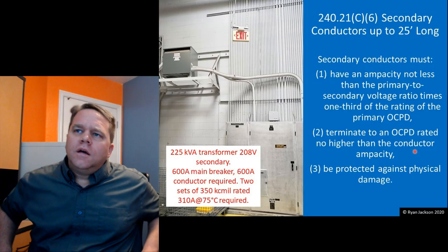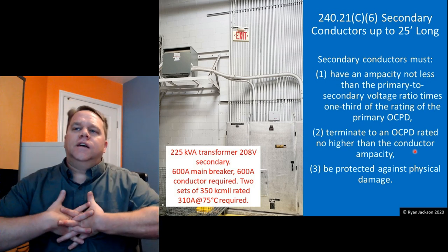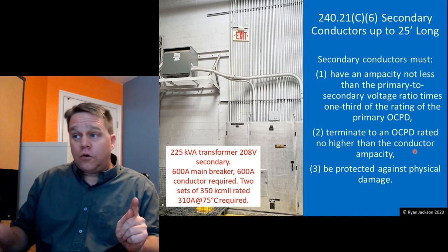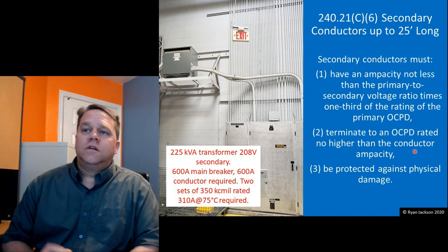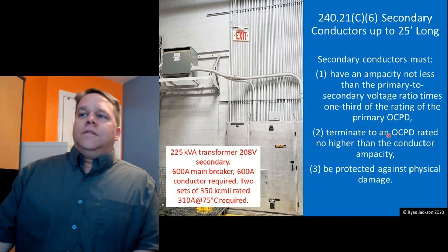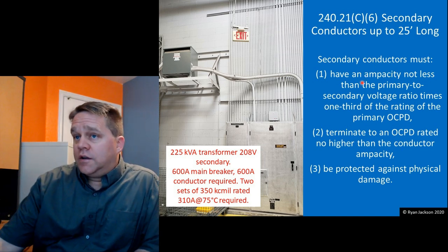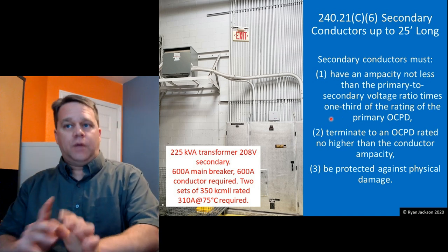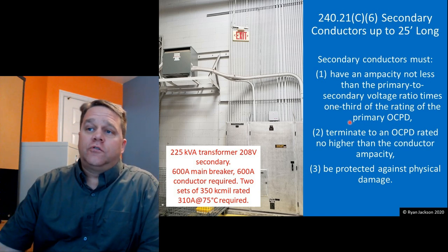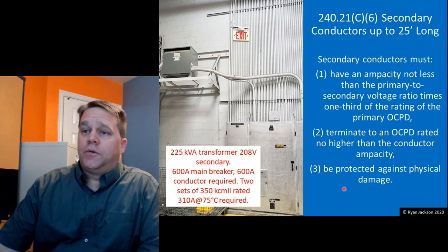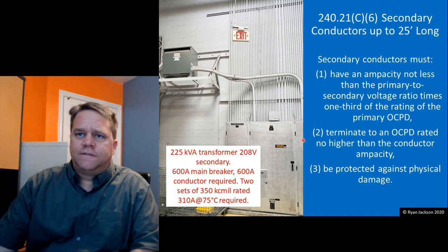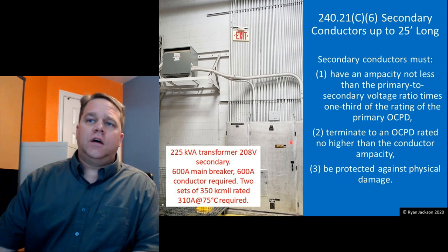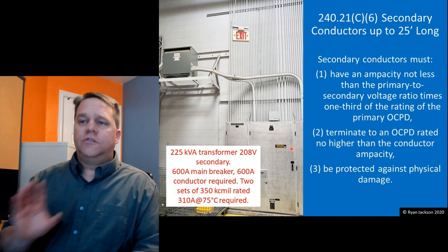The last case is secondary conductors up to 25 feet in length — longer than 10 feet and not outdoors. The rule says the conductors must have an ampacity not less than the primary-to-secondary voltage ratio times one-third the rating of the primary device. They must terminate to an overcurrent device rated no higher than the conductor ampacity, and be protected against physical damage. So the secondary comes out longer than 10 feet but not longer than 25 — you've got to deal with this rule.